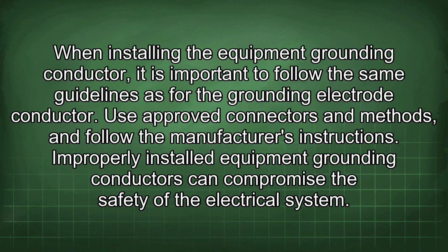When installing the equipment grounding conductor, it is important to follow the same guidelines as for the grounding electrode conductor. Use approved connectors and methods, and follow the manufacturer's instructions. Improperly installed equipment grounding conductors can compromise the safety of the electrical system.